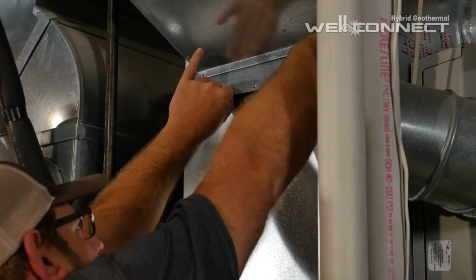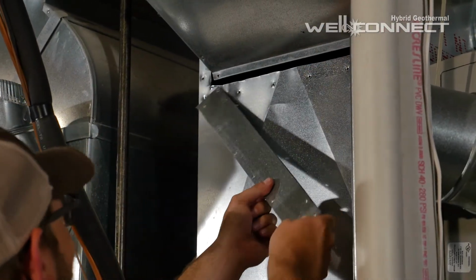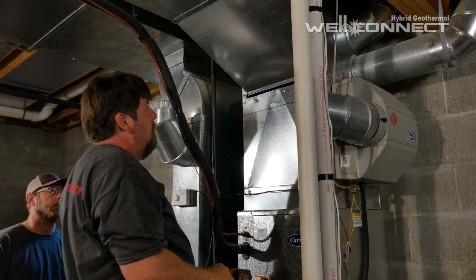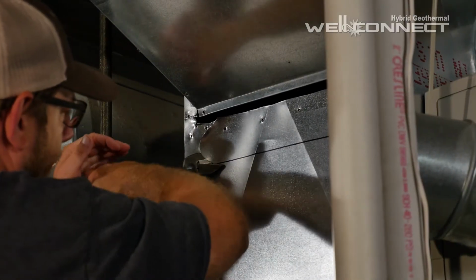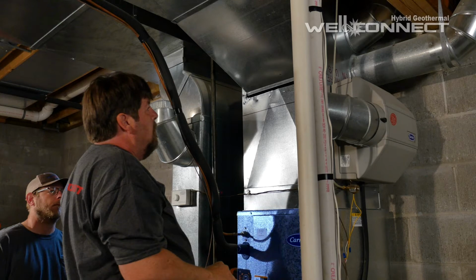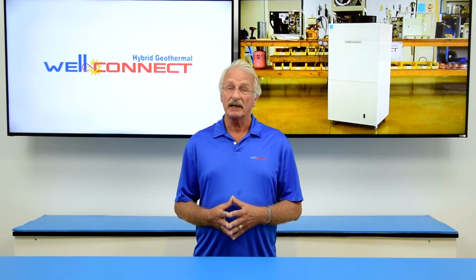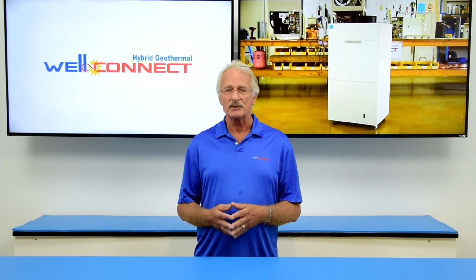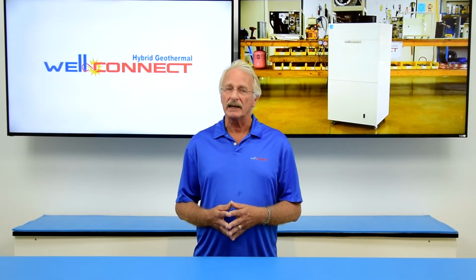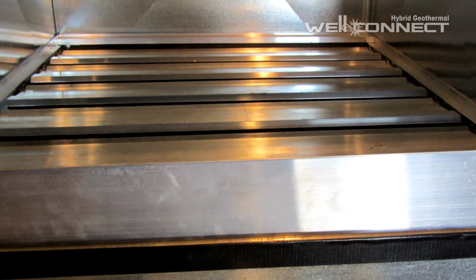The backdraft damper for the furnace is a bit more complicated. First, find an appropriate location in the furnace supply plenum where the damper can be placed and determine the best size damper to fit. If there is an existing AC coil on the furnace, the damper should be placed downstream or above the coil. If the damper is not an exact match for the plenum size, it may be necessary to install some sheet metal angle brackets to support the damper in the plenum. Before closing up the plenum, just make sure the louvers in the damper will open and close freely.